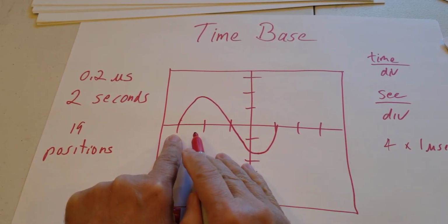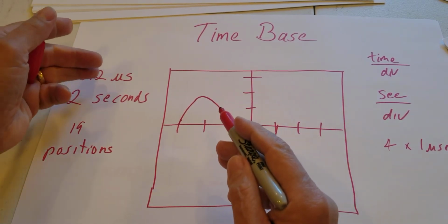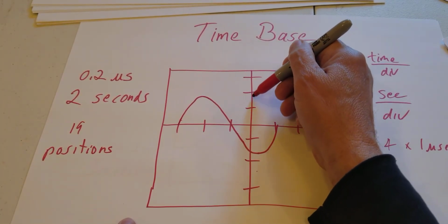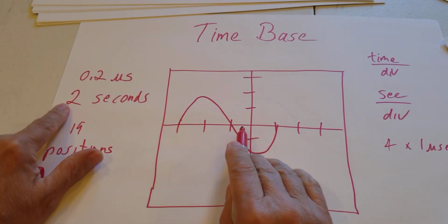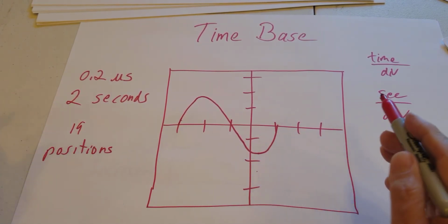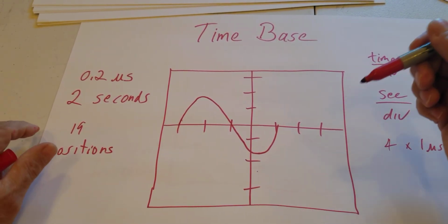So my machine goes from 0.2 microseconds per division to 2 seconds. So it'll literally crawl across the screen like this, 2 seconds, and I can hit another multiplier, make it 20 seconds. It's tortuously slow.